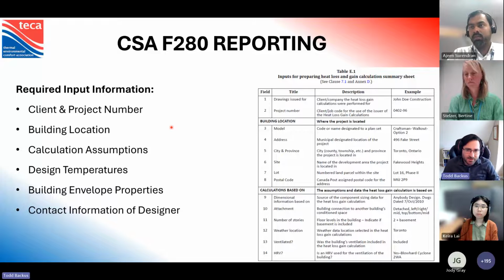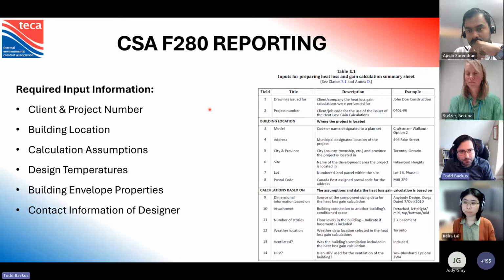So CSA F280 outlines how the information is supposed to be reported from these calculations. Some of the critical information is client and project number, the building location, what assumptions you've made during your calculations, what are the design temperatures used, what building envelope properties you have, as well as the contact information of the designer. And this is actually within CSA, this table that outlines what your obligations are as far as providing information in the report.